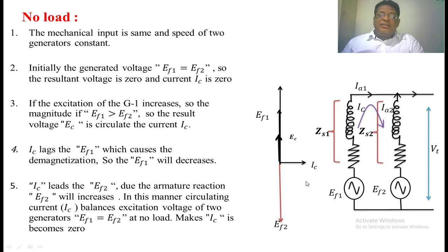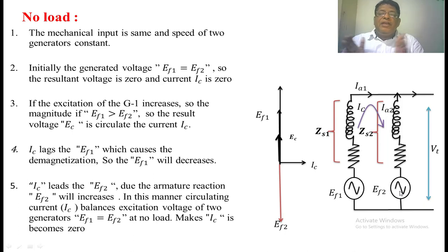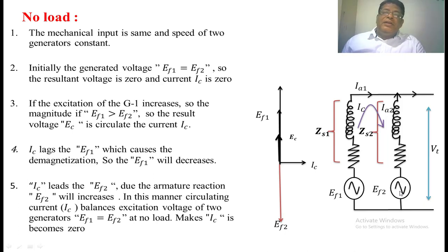Due to the armature reaction, there is a demagnetizing effect in the first generator where EF1 is the excitation. So the net flux will be decreased. With respect to the second generator, the circulating current leads EF2. So due to the armature reaction, the flux in the second generator will be increased, and so EF2 will be increased. In this manner, there is a balance between EF1 and EF2 at no load because of the circulating current, and the resultant voltage in the loop will become zero.